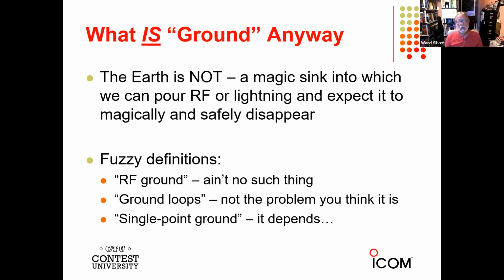The other is ground loops. AC guys, the electricians, they don't like ground loops because that allows error currents to flow, and the error currents can be quite large. Audio guys talk about ground loops because magnetic fields will induce voltage in a closed loop, and that causes a current, and that causes hum or buzz. But generally, if you look behind your equipment, any pair of connections between a couple of pieces of equipment creates a ground loop. There are hundreds of ground loops, even in small stations, and we're not going to get rid of them. So basically, you have to manage what you're doing with your cables and your connections. So I tend to not use the term ground loop, except in very specific instances.